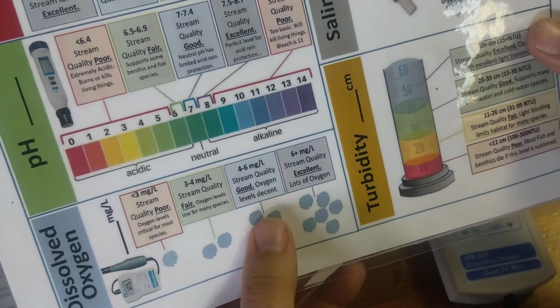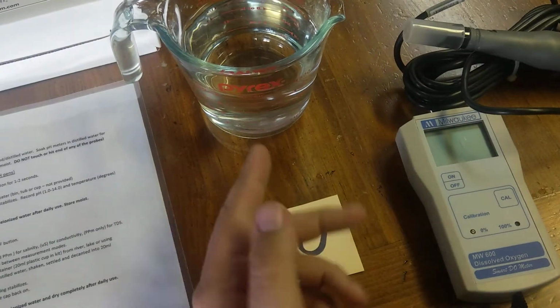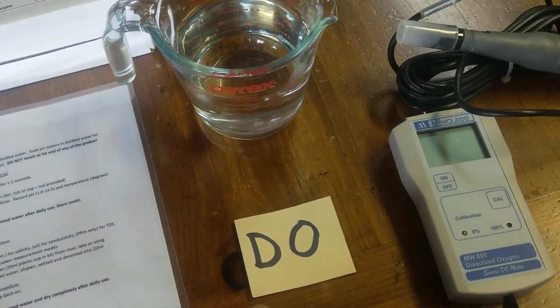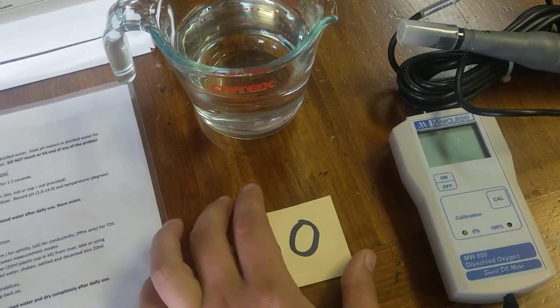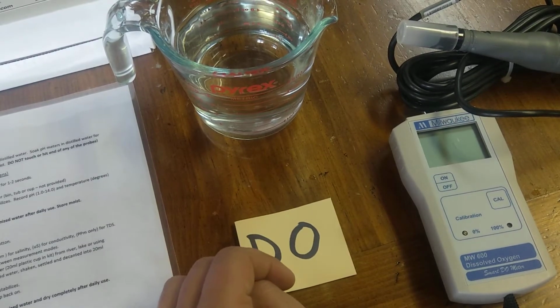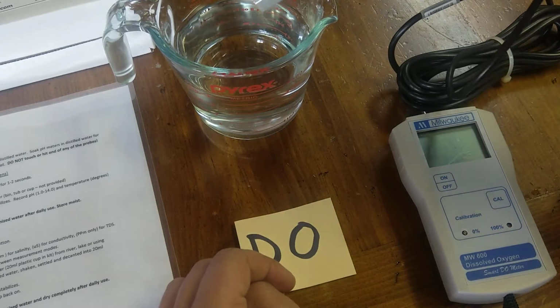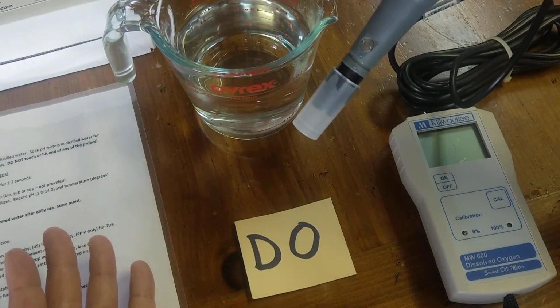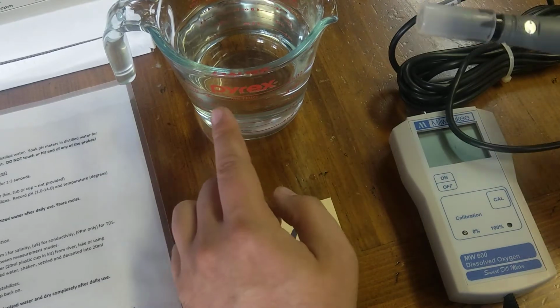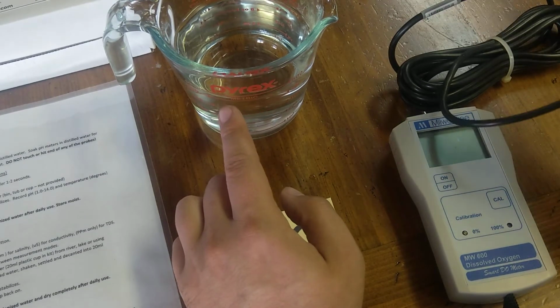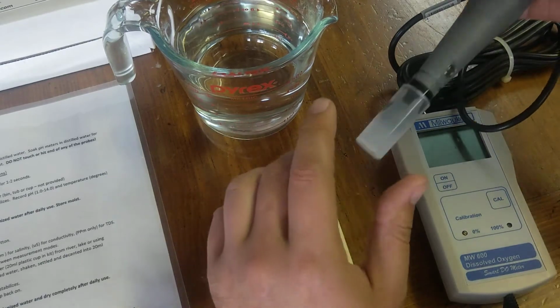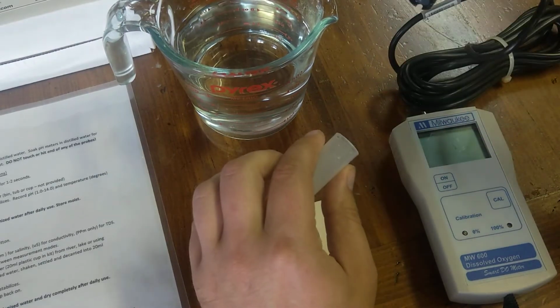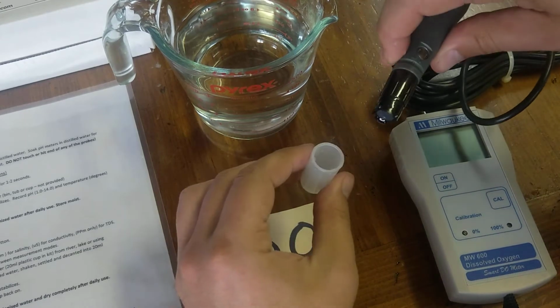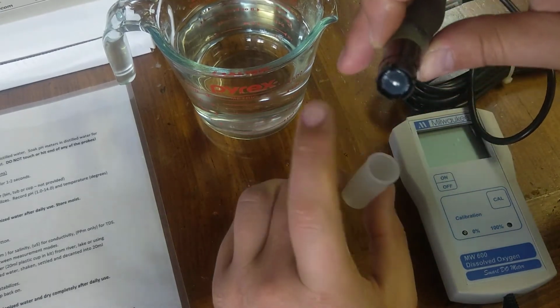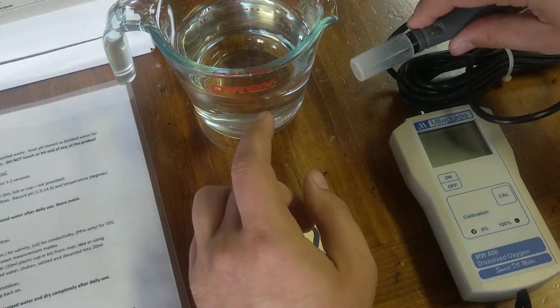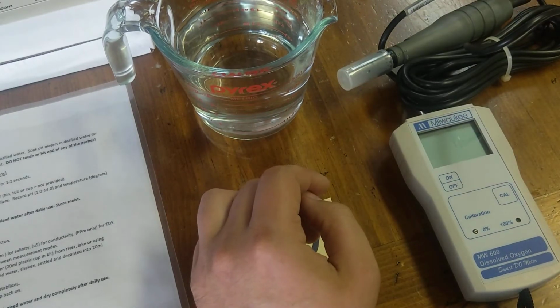A 5.5 is a good water level. This came from the tap, so there was a lot of air included in the sample here. Usually you wouldn't necessarily go directly into the river with this, or stream or pond. You could, but I would highly suggest getting some water from there and then doing your sample, just because if you're near the river, this whole system can fall in. Not to mention you can damage the end of the probe here on rocks and things. So I usually put them in sample containers and take the sample that way.